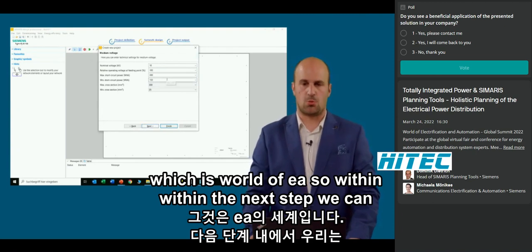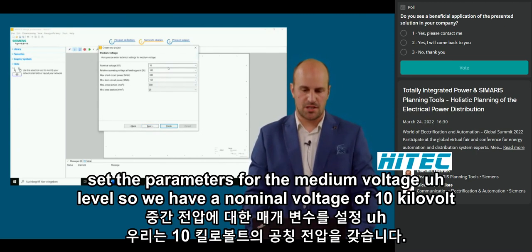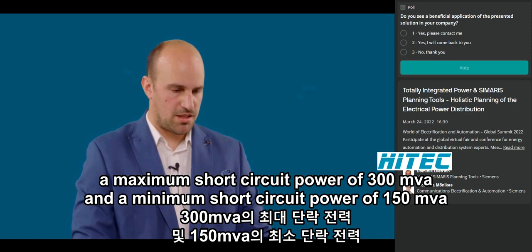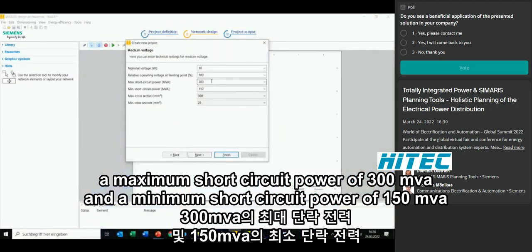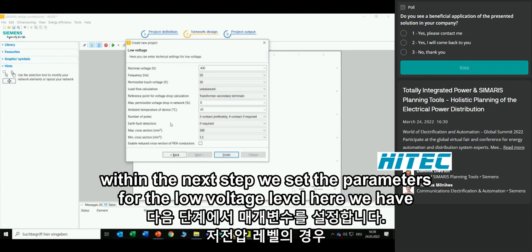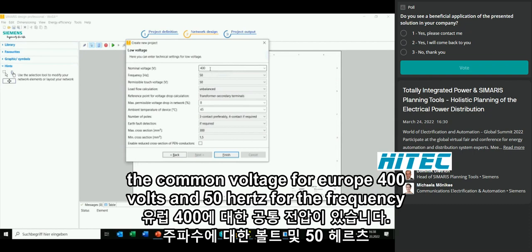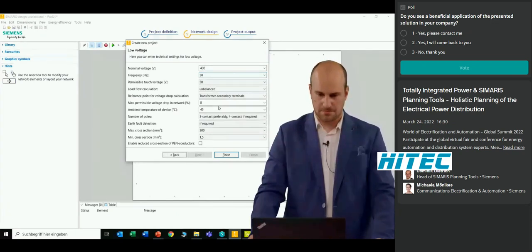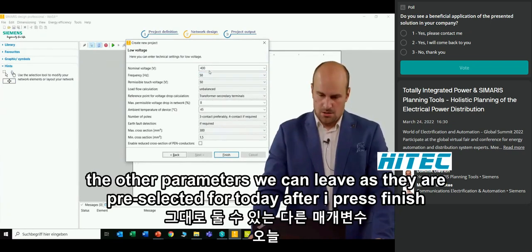Within the next step, we can set the parameters for the medium voltage level: a nominal voltage of 10 kV, a maximum short circuit power of 300 MVA and a minimum short circuit power of 150 MVA. Within the next step, we set the parameters for the low voltage level — the common voltage for Europe, 400 V and 50 Hz for the frequency. The other parameters are pre-selected. After pressing finish, I come directly to my network plan.